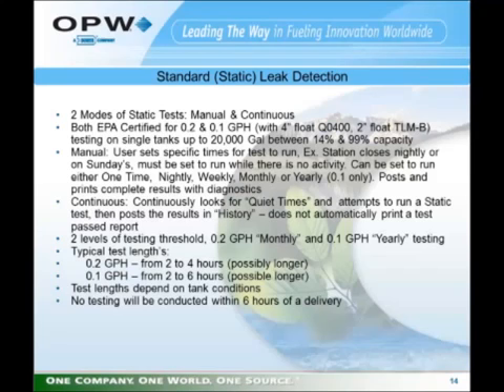A 0.2 gallon per hour test will generally take 2 to 4 hours, but possibly longer. A 0.1 gallon per hour test will take from 2 to 6 hours and sometimes possibly longer. The test lengths do depend on the tank conditions. The unit will determine the length of the test when, at the start of the test, it looks at the size of the tank, it looks at the volume in the tank, and it looks at the temperature. At that point, it determines how long that test will run.